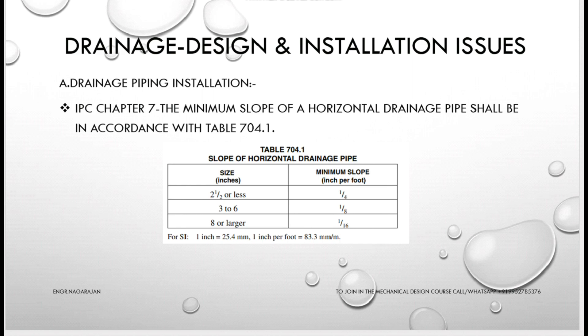As per IPC (International Plumbing Code), the minimum slope of a horizontal drainage pipe shall be in accordance with Table 704.1. For pipe sizes 2.5 inches and less, the minimum slope is 1/4 inch per foot. For 3 to 6 inch pipes it is 1/8 inch per foot, and for 8 inch and larger it is 1/16 inch per foot.